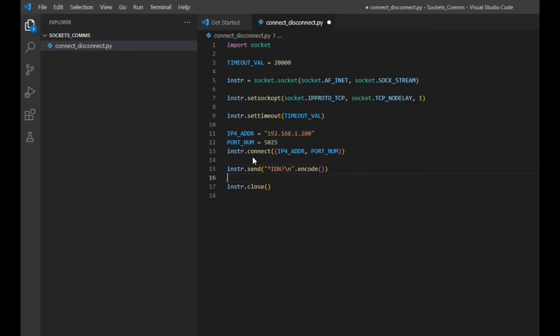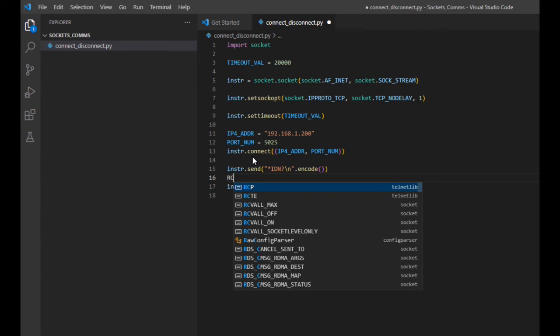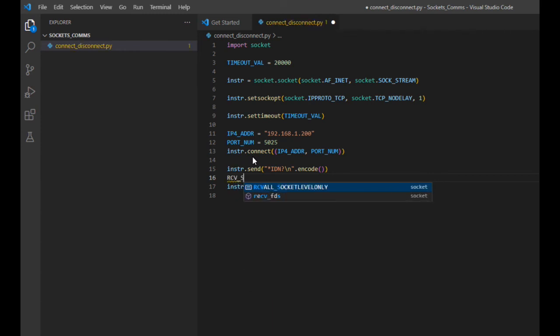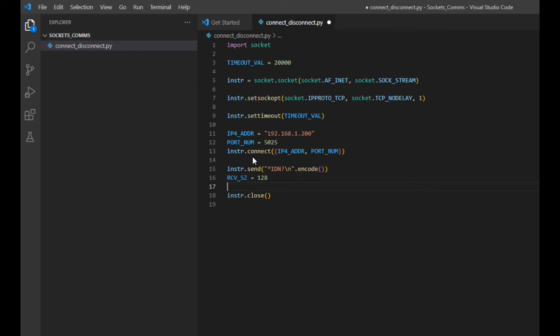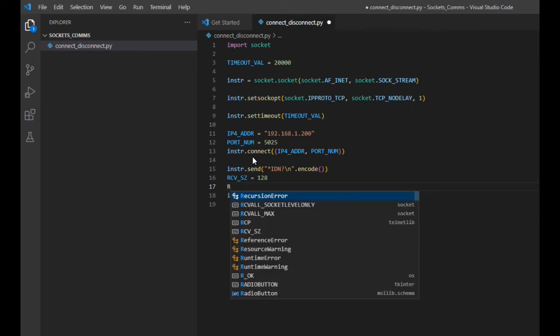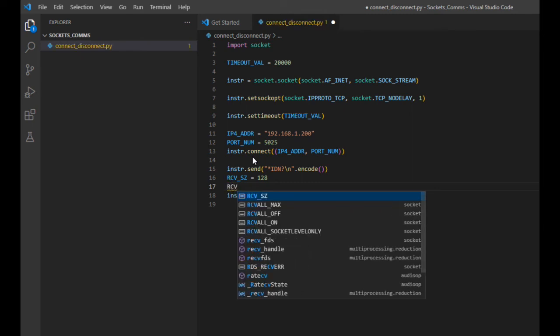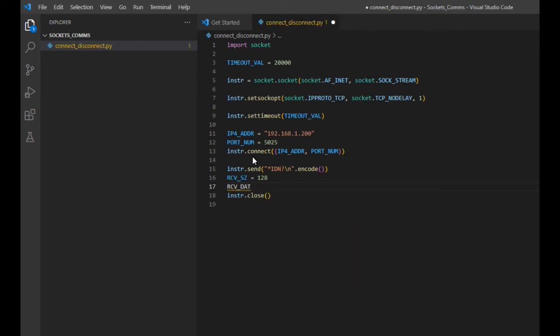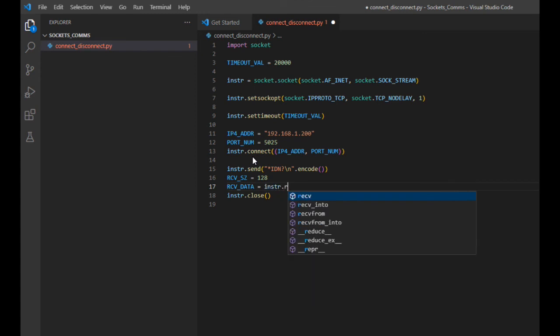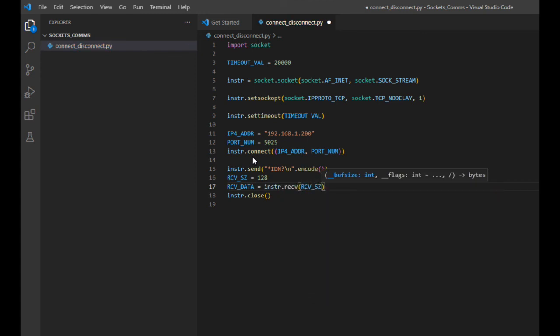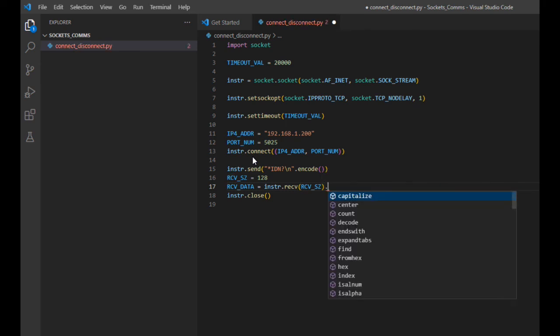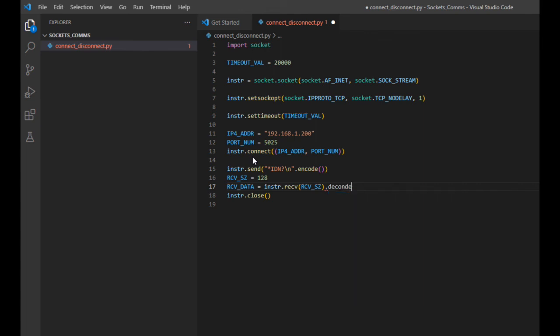Almost immediately after receipt of the command, our instrument will be ready with a response in its output queue. Let's first define a constant that will indicate the approximate length of data that we expect to receive. As a rule of thumb, it's best to overestimate or we risk losing part of our data. To extract this response, we'll need to use the receive method. Let's define a variable to hold the string response from our instrument, then use the receive method to pull the data off the instrument and over onto our controlling PC.